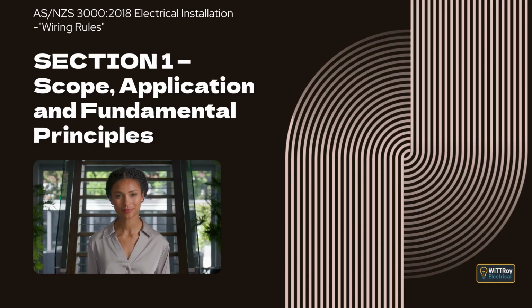Clause 1.4.12 is appliance, portable. This is an appliance that can be moved while it is operating, or one that can be moved easily from one place to another even when it is connected to the supply. Clause 1.4.13 is appliance, stationary. This is either a fixed appliance or an appliance that weighs more than 18 kilograms and does not have a carrying handle. Clause 1.4.14 is arc fault detection device. This is a device that detects arcing faults within the installation wiring or the plug and lead connection of electrical equipment. When an arc fault is detected, the device disconnects the circuit.